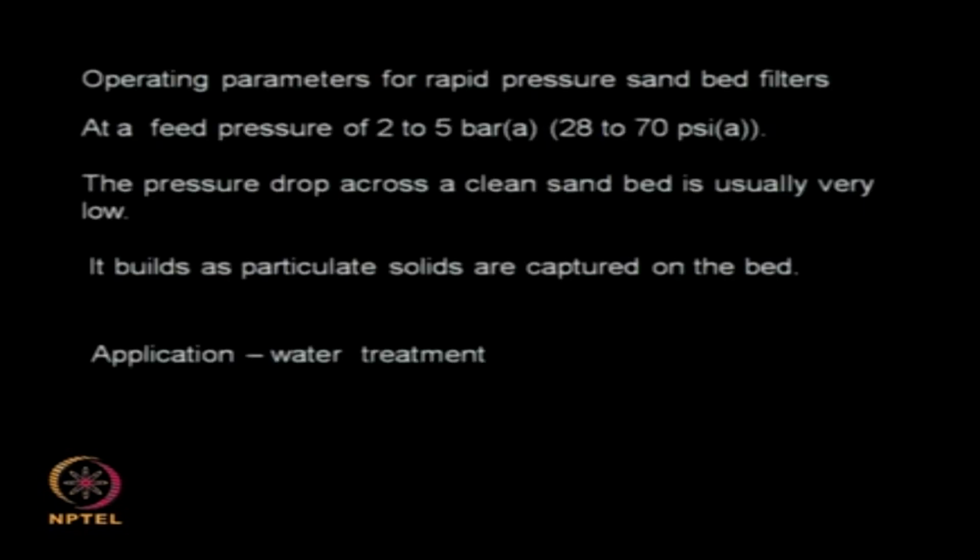So for the operating parameters for rapid pressure, it can be operated at very low pressures, 2 to 5 bar maybe. Generally if the entire sand bed is very clean, the pressure drop also will be minimal, but over a period of time, if you are accumulating wasteful material, if there is biological growth taking place, then slowly you may find that the pressure drop across these increases.